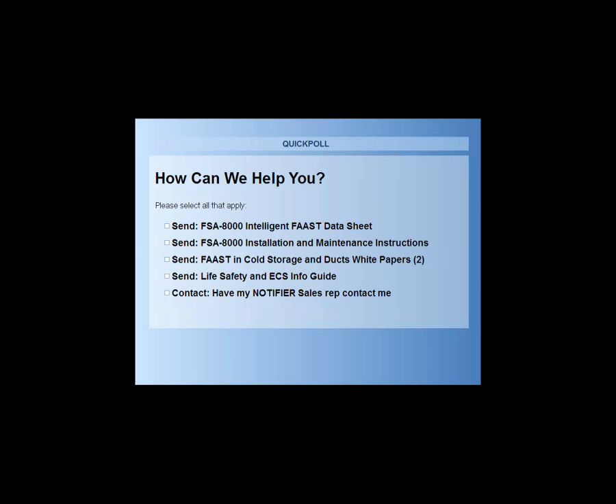So if a hole gets covered up or holes start getting blocked, the ultrasonic sensors in the FAAST inlet are going to say, okay, I'm seeing less airflow now. And when we get to 20% off of our baseline, the FAAST will actually initiate that low airflow fault. Looking at the front of the FAAST device, I'm not sure we had a good picture of it during the webinar, but we do have a 10-segment airflow reader on the front of the UI, which can be viewed right at the detector or using Pipe IQ. As airflow starts to deviate from that baseline, the readout will either move to the left in the case of a low flow or to the right in the case of a high flow for a breakage.